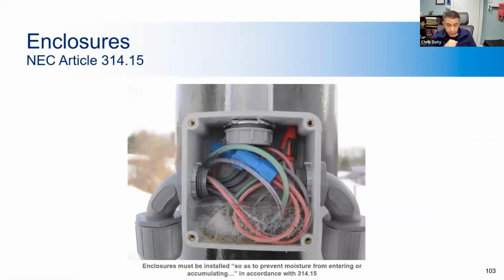Here we have an interesting situation. We have an outdoor rated enclosure that was simply not installed properly. You can't really see it in this picture, but the conduit entry point isn't properly sealed at the top of this enclosure. So what you have is water that gets down into the enclosure, and it pools in the bottom of the junction box, and eventually it gets high enough that it drains down one of the side conduits, and then it's going through your electrical system, potentially causing havoc. So you want to avoid that at all costs.